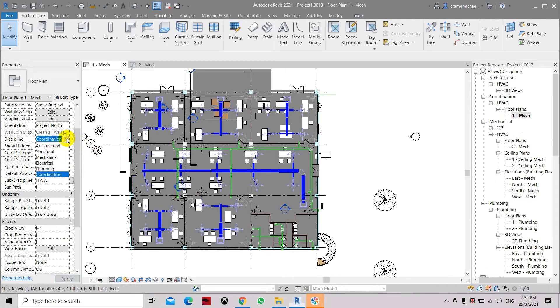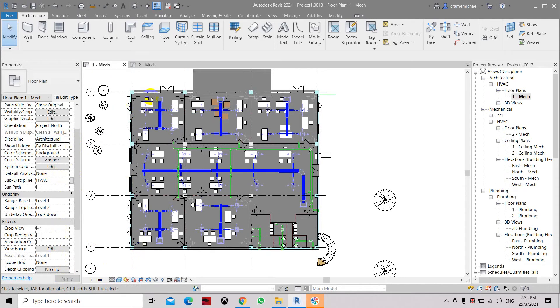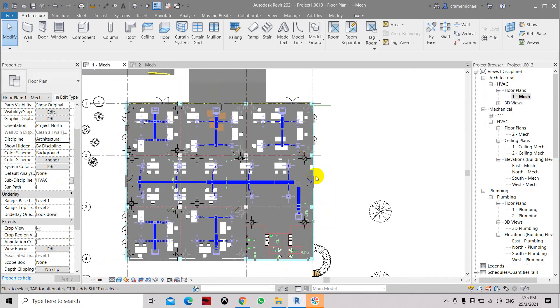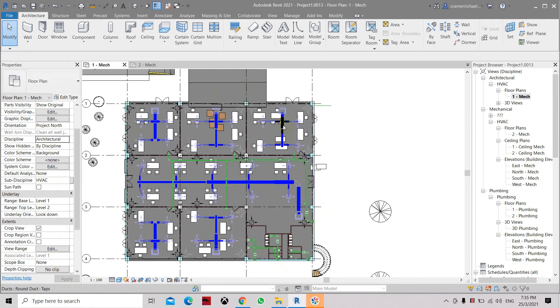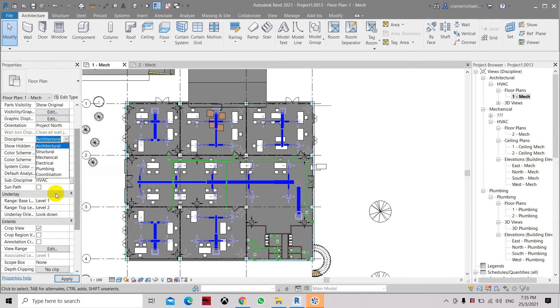So that is how to resolve this issue once you have encountered that some of your drawings or layouts in the mechanical system suddenly disappear when you change the discipline properties. It will be resolved with the view range base level and range top level settings.